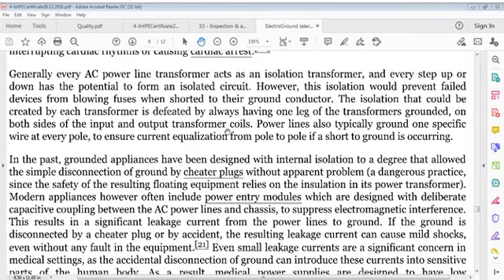Generally, every AC power line transformer acts as an isolation transformer, and every step up or down has the potential to form an isolated circuit. However, this isolation would prevent failed devices from blowing fuses when shorted to their ground conductor. Isolation that could be created by each transformer is defeated by always having one leg of transformers grounded on both sides of input and output transformer coils.